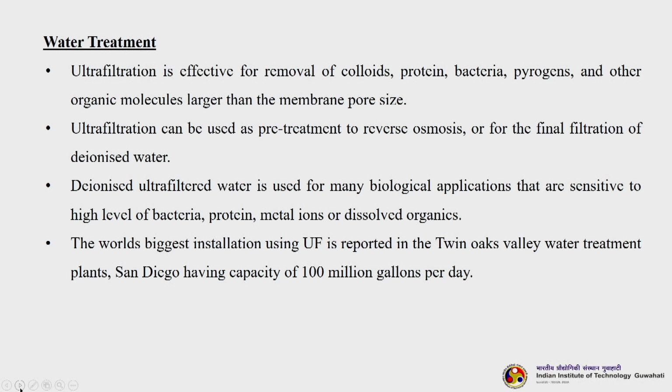It can be used as a pre-treatment to reverse osmosis or for the final filtration of the deionized water. Now, deionized ultrafiltered water is used for many biological applications that are sensitive to high level bacteria, protein, metal ions or dissolved organics. The world's biggest installation using ultrafiltration is reported in the Twin Oaks Valley water treatment plant, that is in San Diego, having a capacity of 100 million gallons per day.